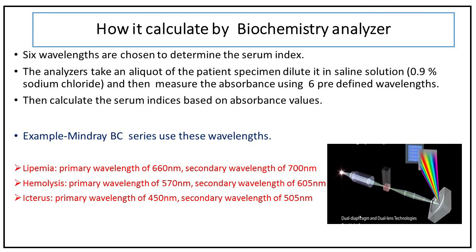Serum indices can also be calculated by a fully automated biochemistry analyzer. Technical advances utilizing spectrophotometric measurements on fully automated chemistry analyzers allow rapid and accurate identification of serum indices. The analyzer takes an aliquot of the patient specimen diluted in saline solution (0.9% sodium chloride), measures the absorbance using six predefined wavelengths, and then calculates the serum indices based on those absorbance values.